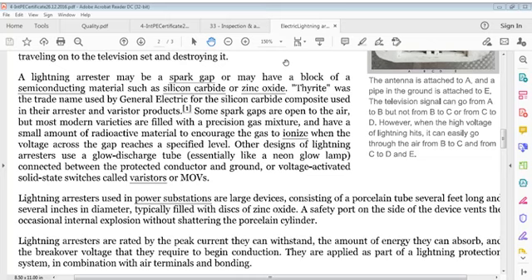Some spark gaps are open to air, but most modern varieties are filled with a precision gas mixture and have a small amount of radioactive material to encourage the gas to ionize when the voltage across the gap reaches a specified level. Other designs of lightning arresters use a glow discharge tube, essentially like a neon gas lamp, connected between the protected conductor and ground, or voltage activated solid state switches called varistors or MOVs.